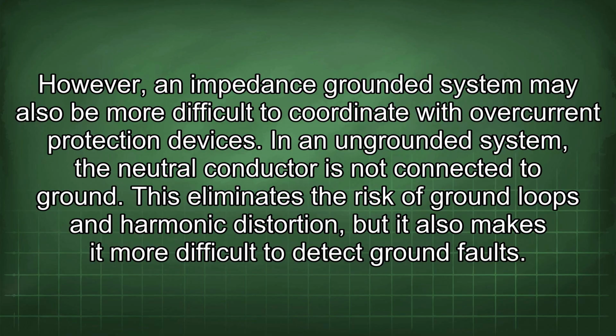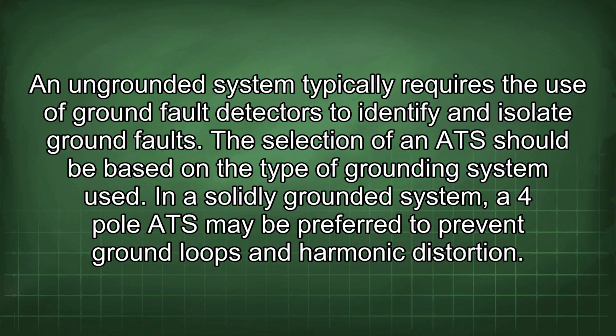In an ungrounded system, the neutral conductor is not connected to ground. This eliminates the risk of ground loops and harmonic distortion, but it also makes it more difficult to detect ground faults. An ungrounded system typically requires the use of ground fault detectors to identify and isolate ground faults.